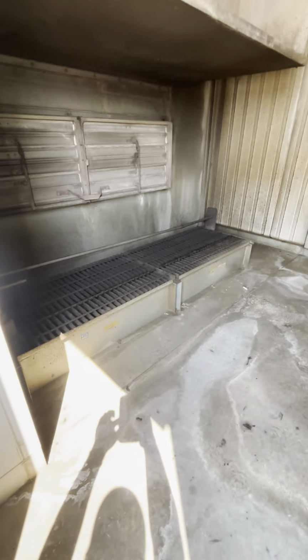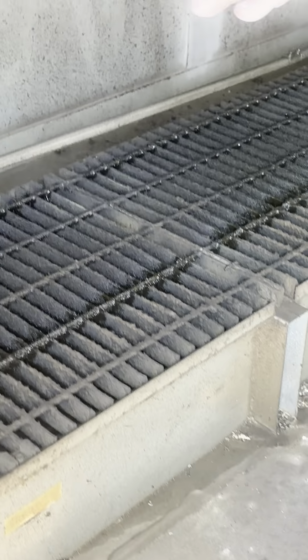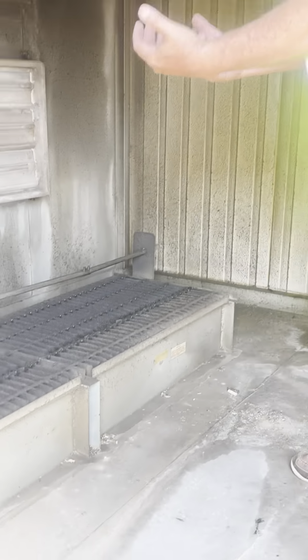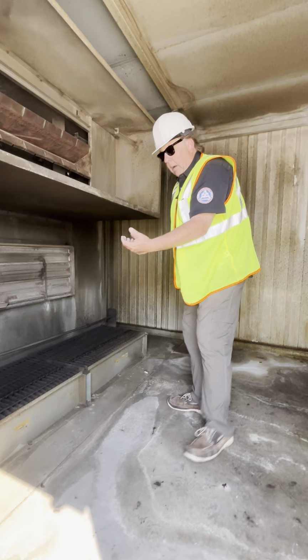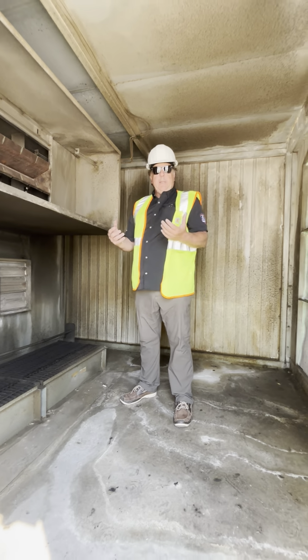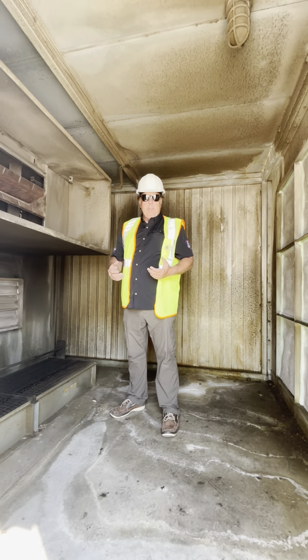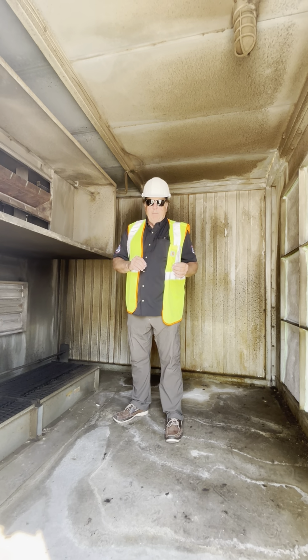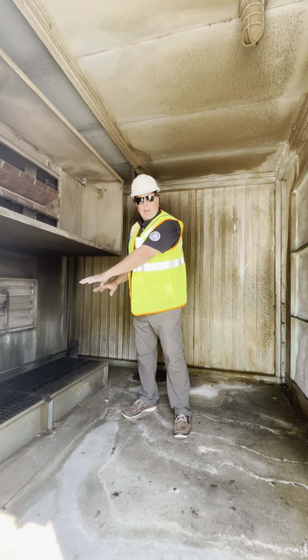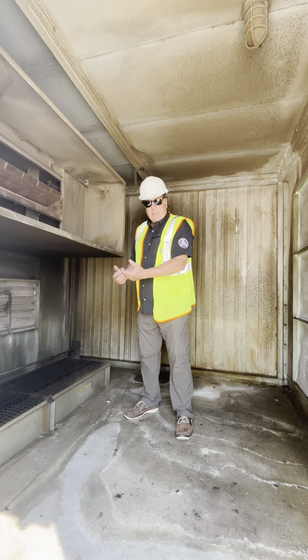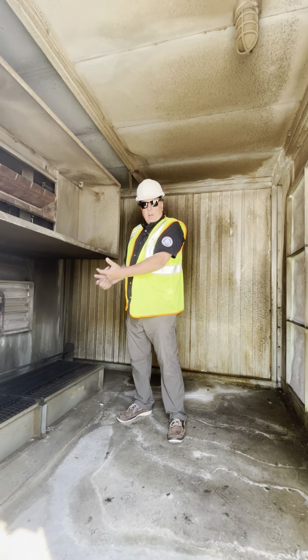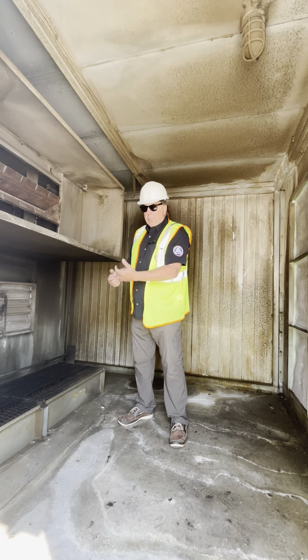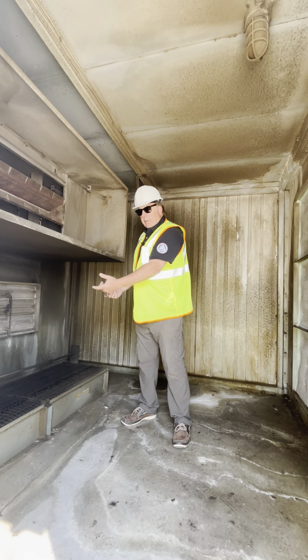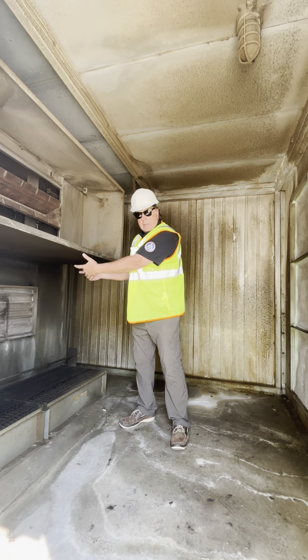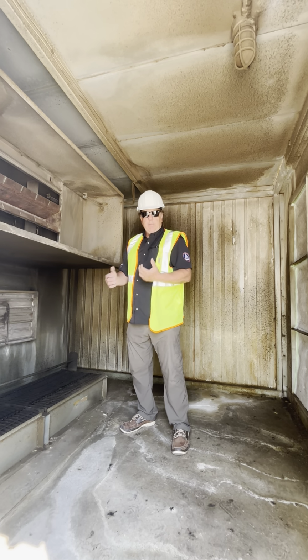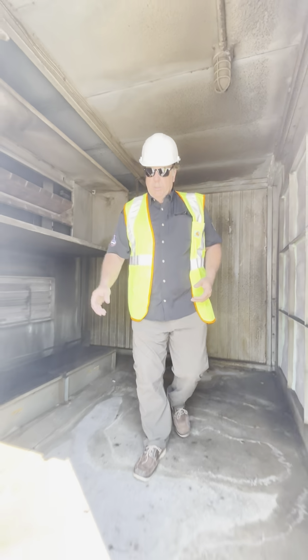The grating on the floor that you're seeing now, all down in here, this is coming from the building down below. We have the option on this machine. This is actually considered a variable air volume machine, not by slowing down the fan, but by limiting the amount of air that can come through these dampers. So we have the choice of recirculating the air from the building, or we can bring it from the building and open up outside dampers and bring air in from the outside. So we have a lot of control over what we can do with this machine.